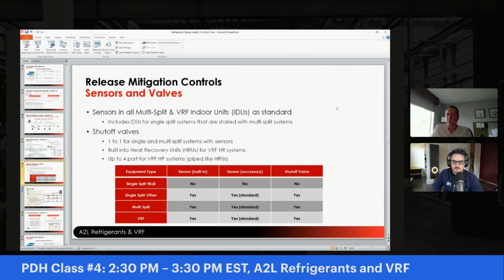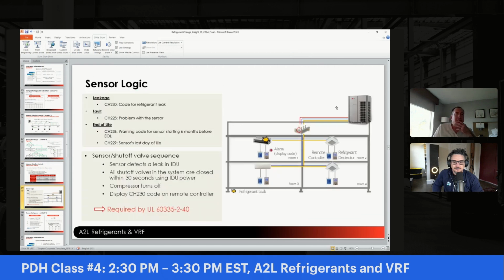So, getting into the sensor logic, this is an example of our system, and we're going to have 4 different error codes actually. So you've got one code for when you have a refrigerant leak, but then we had to get another code in case there was just a fault or a problem with the sensor itself. And then these sensors are good for 10 years, but 6 months before its end of life, you're going to get a different code to tell you that time is running out. And then on the last day of its life, it will throw a different code to tell you you're done. You need to go replace me.